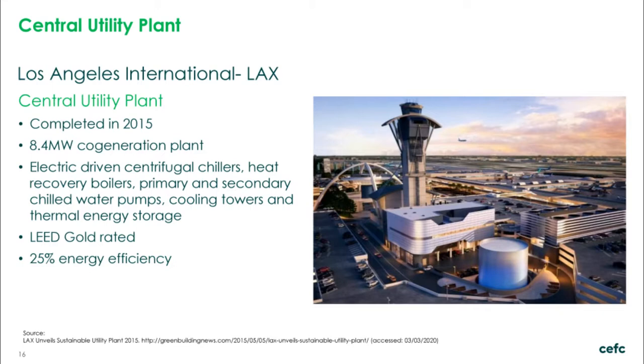In 2015, Los Angeles International Airport completed construction of their new central utility plant, consisting of a 4-story building for plant and staff offices, an above ground cylindrical chilled water storage tank, and a low-rise structure with maintenance shops and cooling towers. The plant included electric-driven centrifugal chillers, heat recovery boilers, primary and secondary chilled water pumps, cooling towers, and thermal energy storage. It included an 8.4 megawatt cogeneration plant to provide electricity and waste heat to drive additional steam-driven chillers. The systems and components were designed to achieve a LEED Gold rating, and it replaced a 50-year-old plant.